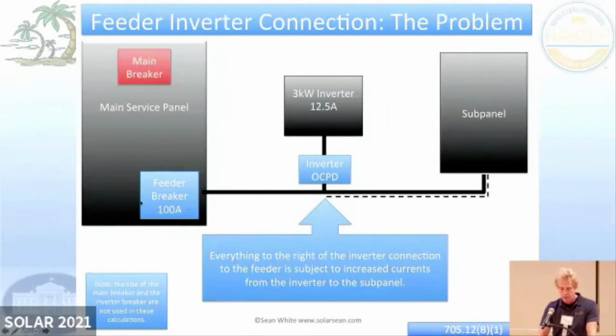So what you have here is the feeder breaker, and this has 100 amps to it. We're protecting this conductor so it doesn't have more than 100 amps going on it. And then all of a sudden somebody pops in an inverter and they're adding another 12.5 amps here. There's going to be times where we have extra current going from that inverter. If we turned off this sub panel, the most you get going that direction is 12.5 amps. So that's not a problem.